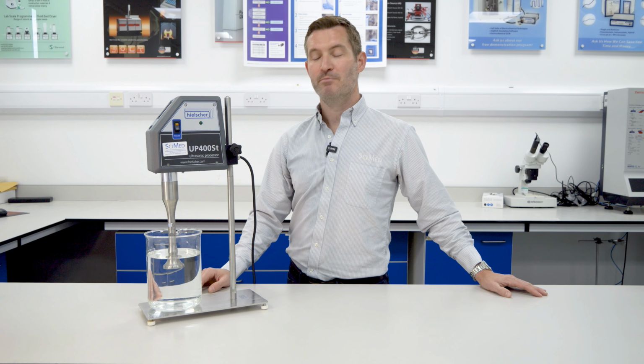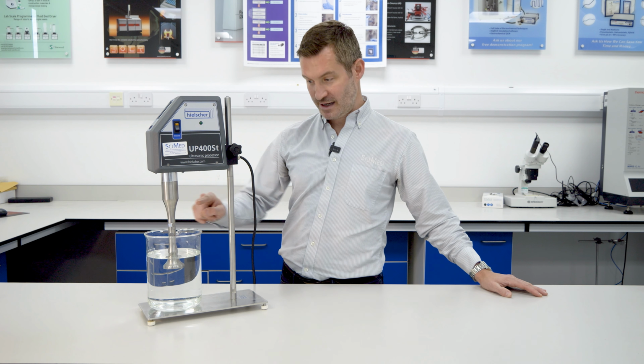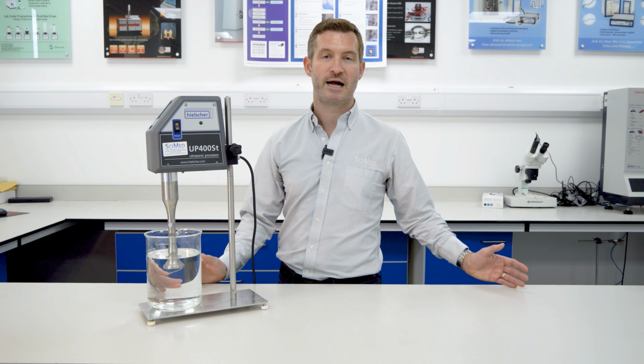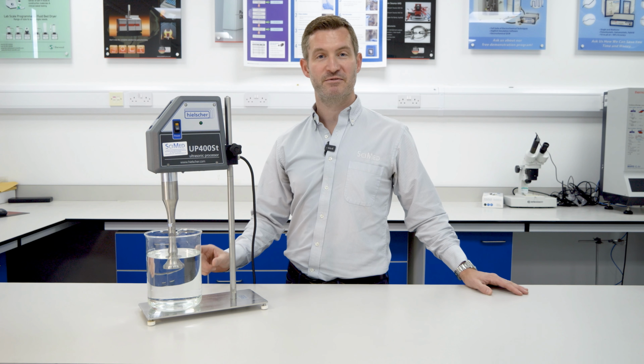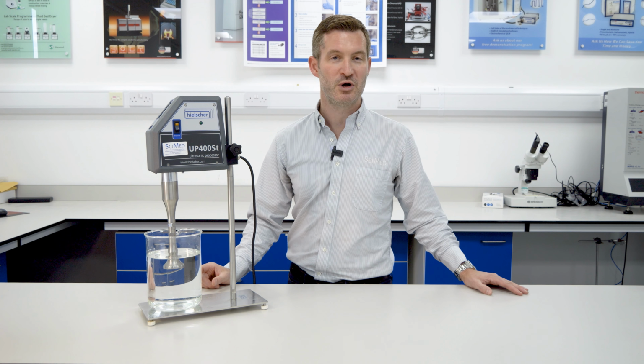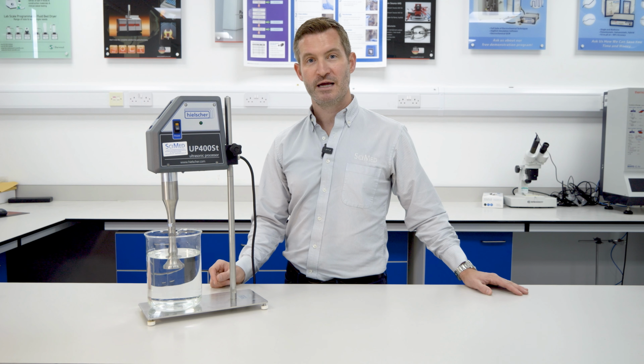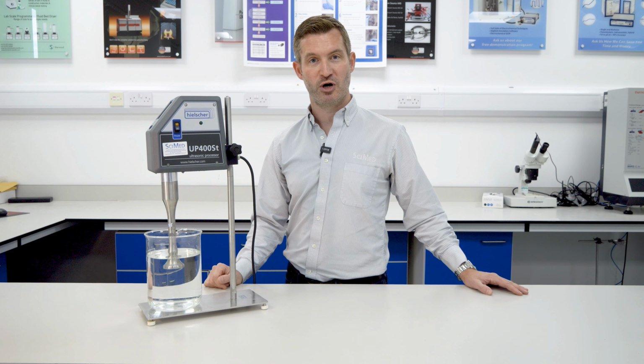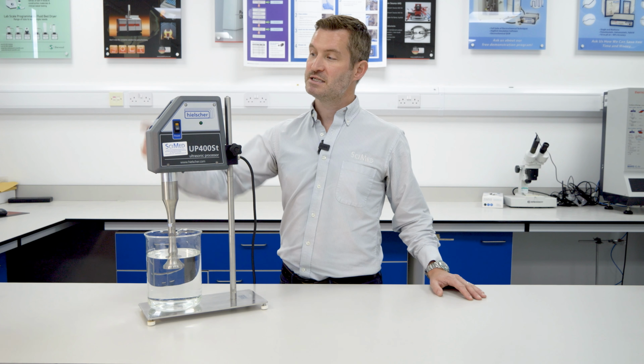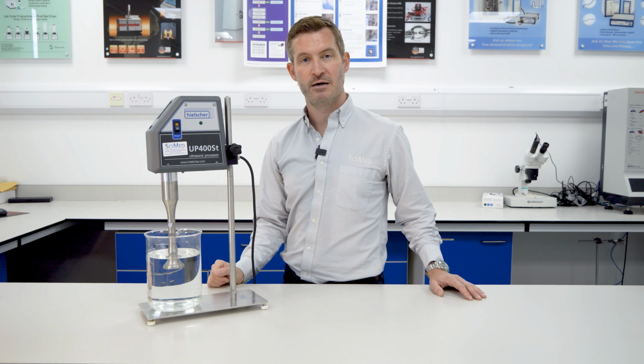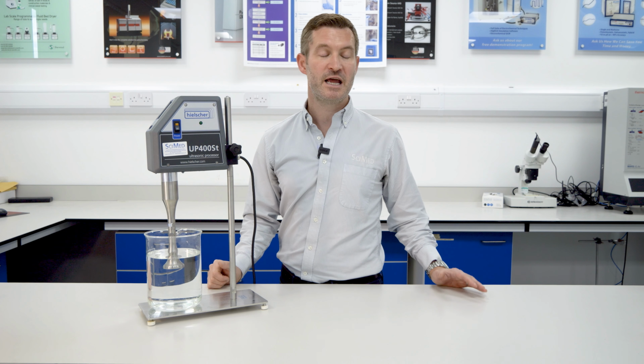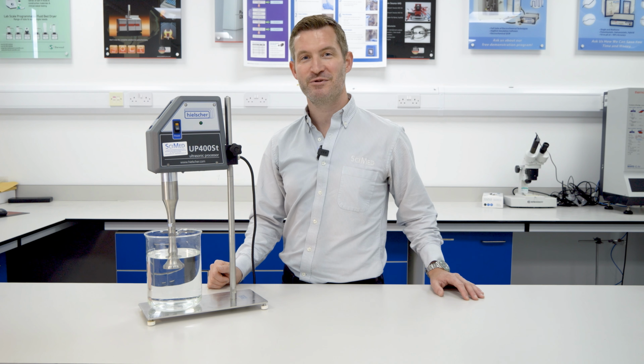The only moving part on this unit is the probe—it's not even classed as a machine, it's a device because there's just one moving part. All you need to do, when you change this probe (which may be once every 2 years), is go to the settings button, go one menu down, hit calibrate, and it does everything else for you.